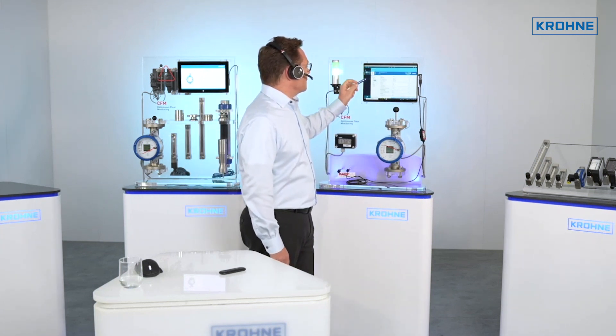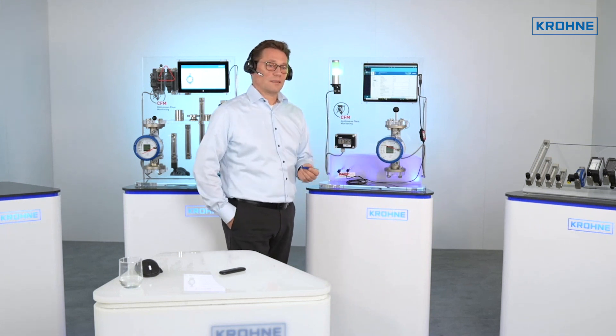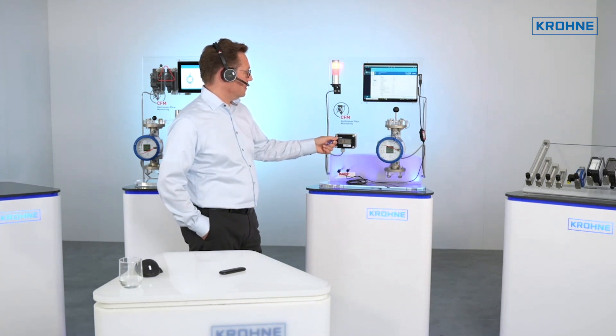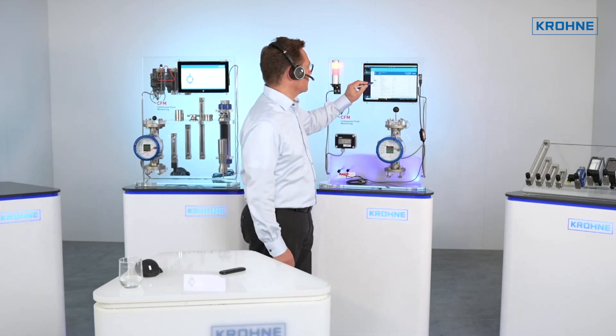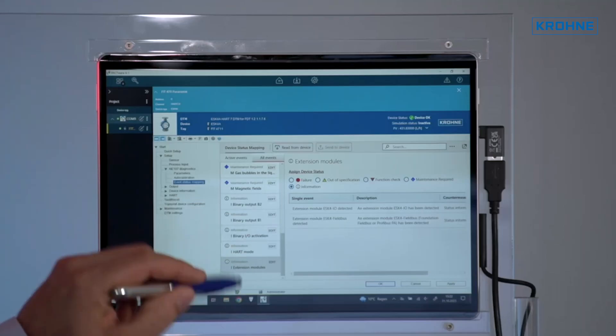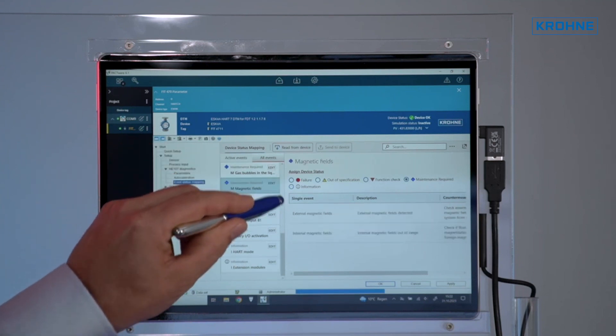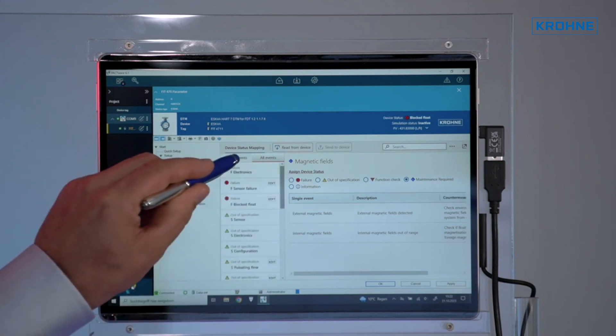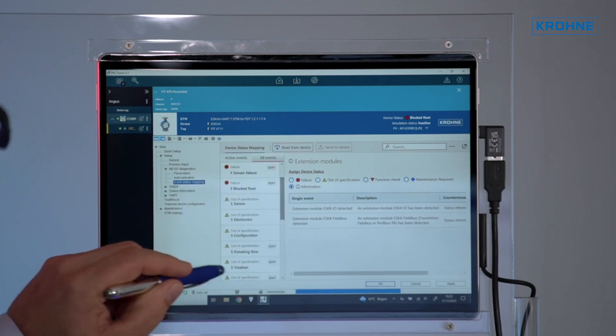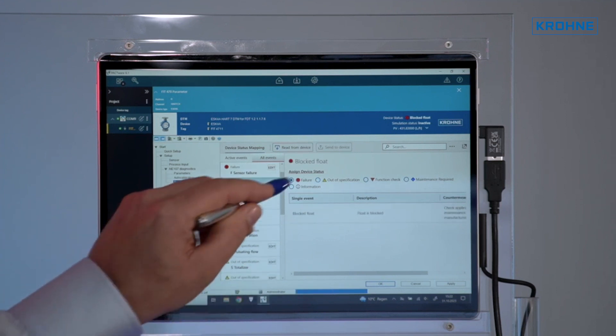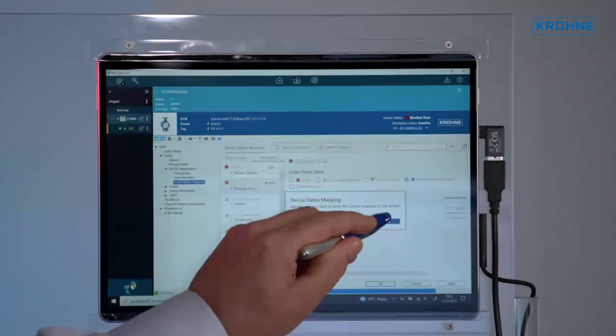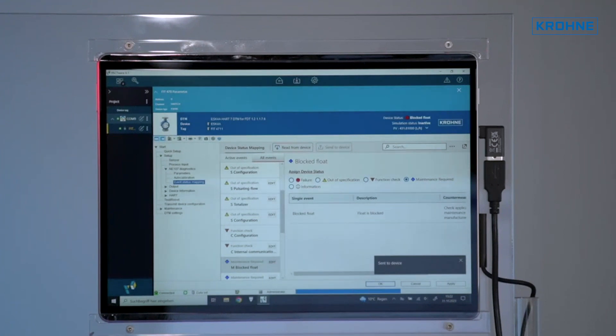The event can be mapped to different states. It can be used as 'failure', in which case the output is driven to fail high. But you can also change the mapping of the diagnostics if you want to keep the current signal. Going to event status mapping and finding 'blocked float' — at the moment it's mapped as failure, but I can change it to 'maintenance required' and send it to the device.